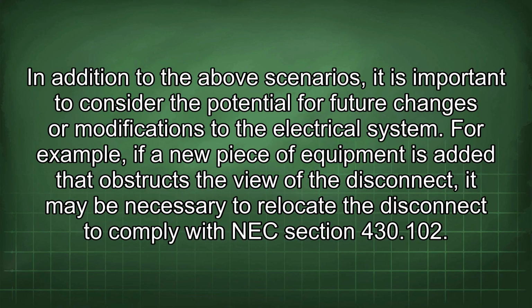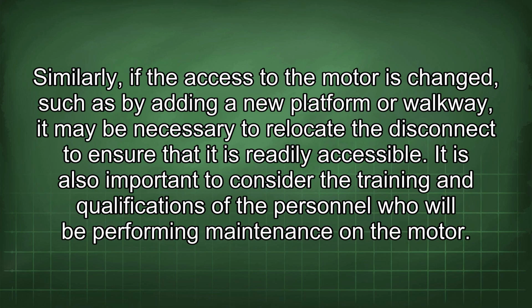In addition to the above scenarios, it is important to consider the potential for future changes or modifications to the electrical system. For example, if a new piece of equipment is added that obstructs the view of the disconnect, it may be necessary to relocate the disconnect to comply with NEC section 430.102. Similarly, if the access to the motor is changed, such as by adding a new platform or walkway, it may be necessary to relocate the disconnect to ensure that it is readily accessible.